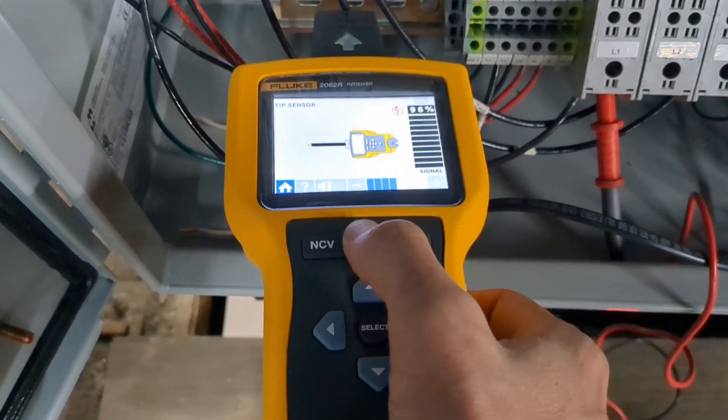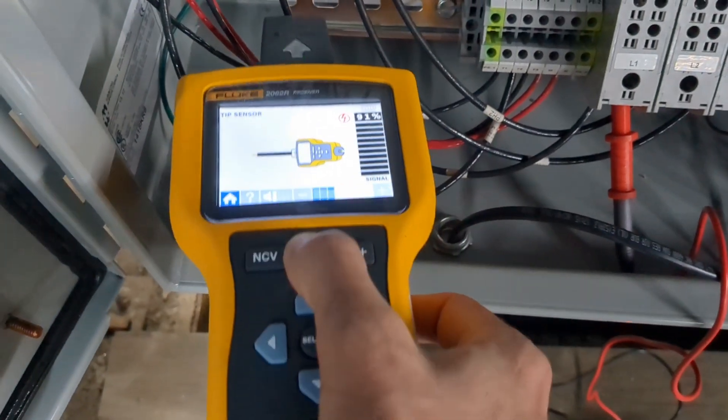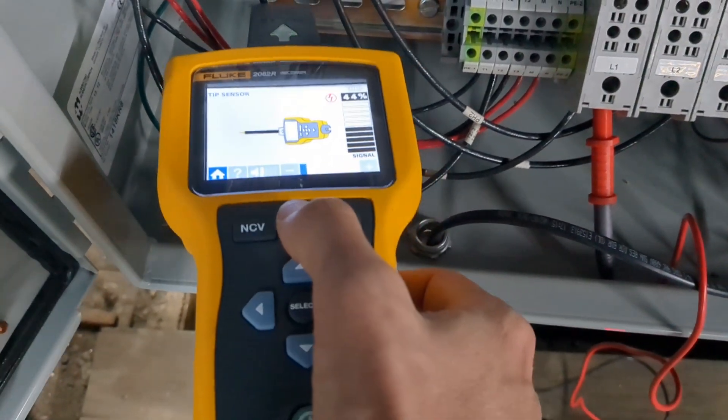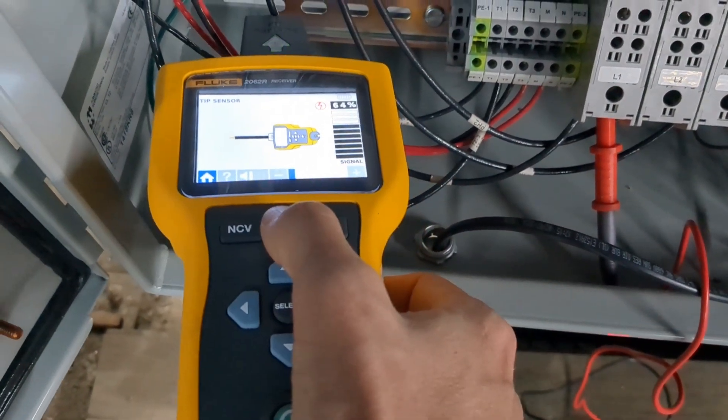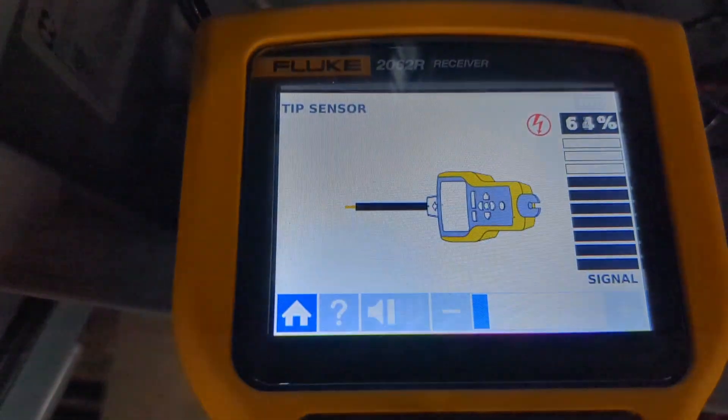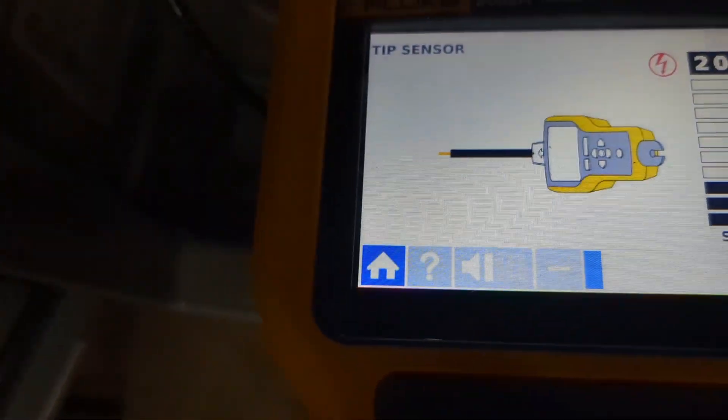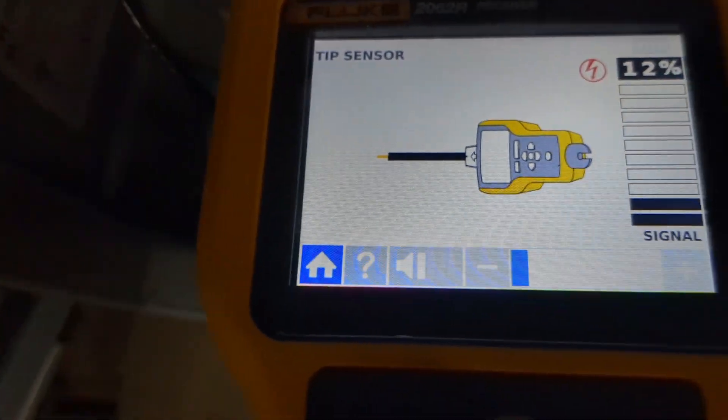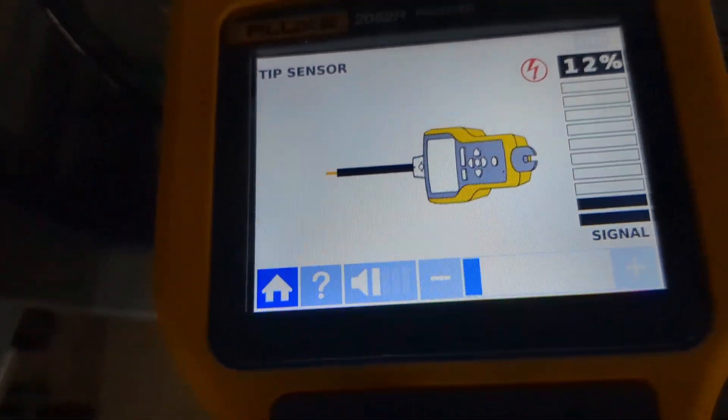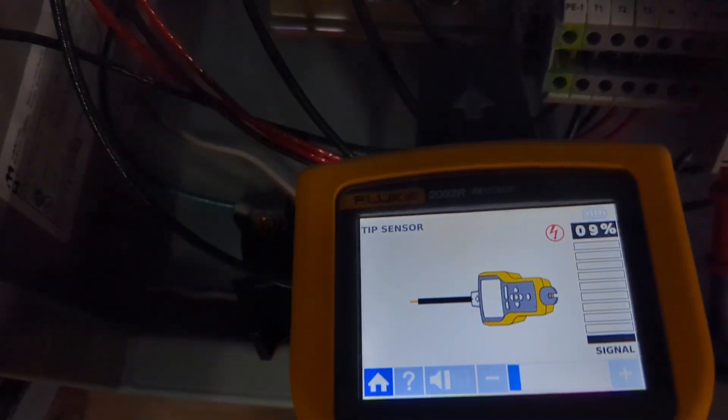Right now you can see I'm maxing out. I'm going to put on three phases that are the inputs and I'm adjusting the sensitivity and you can see I get a stronger signal from the phase that it's hooked up to and lower signal on the other two phases.